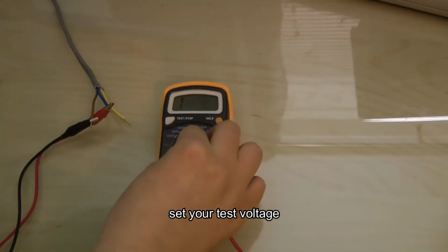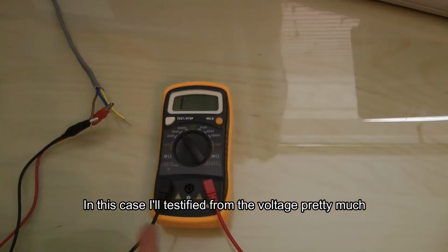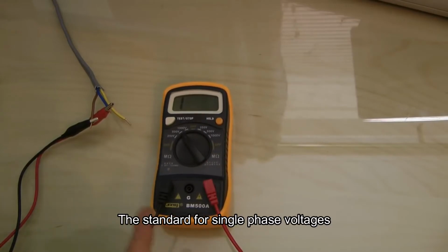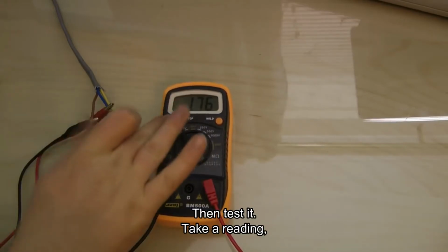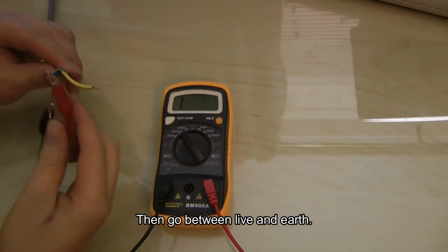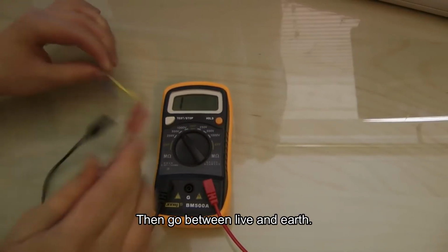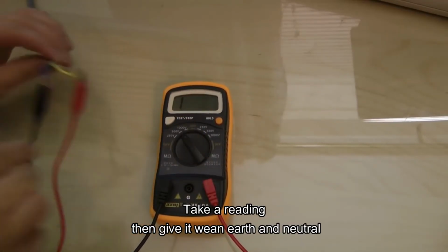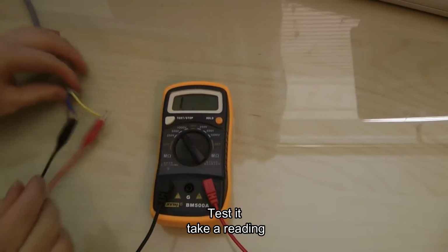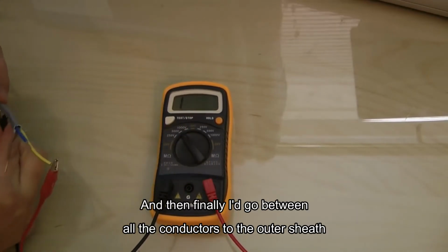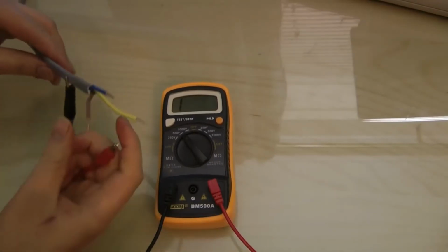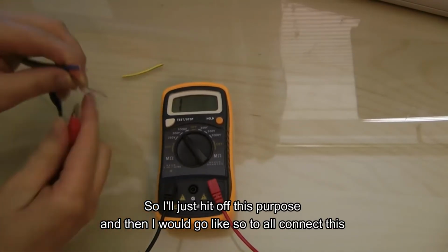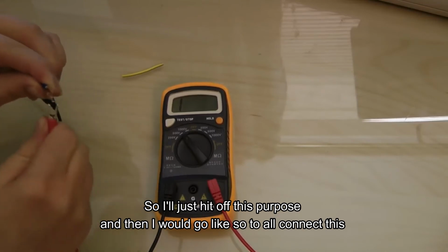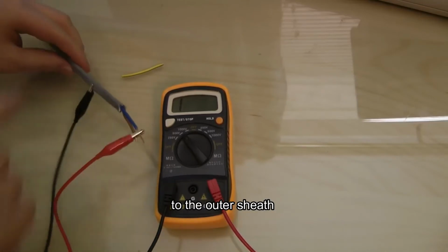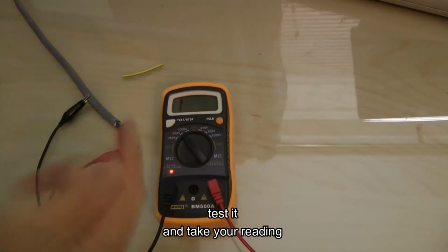Set your test voltage. In this case, I will set it to the standard single phase voltage. Then test it. Take a reading, then go between live and earth. Test it. Take a reading, then go between earth and neutral. Test it. Take a reading, and then finally go between all the conductors and the outer sheath. So I will just join these together and connect this to the outer sheath. That's it, and take your reading.